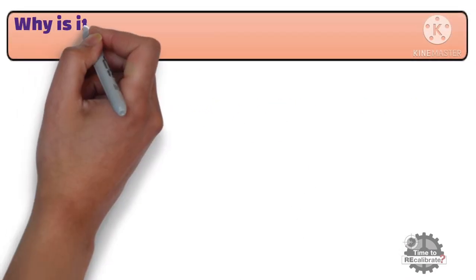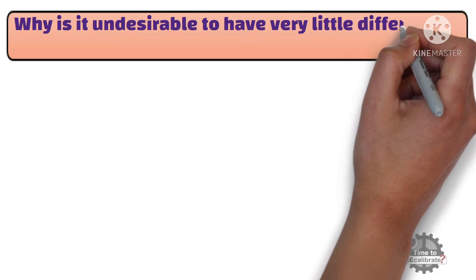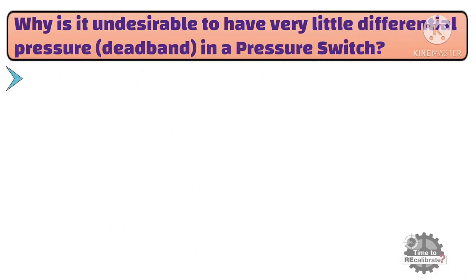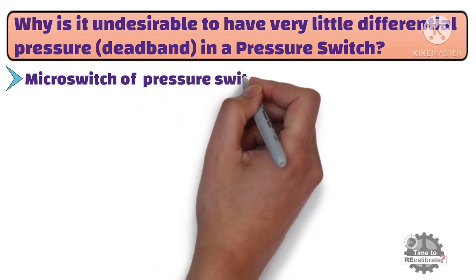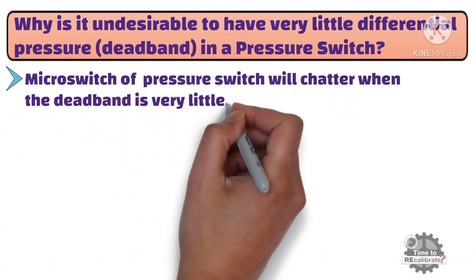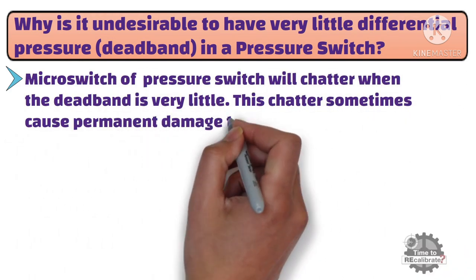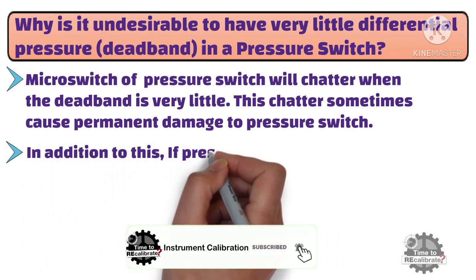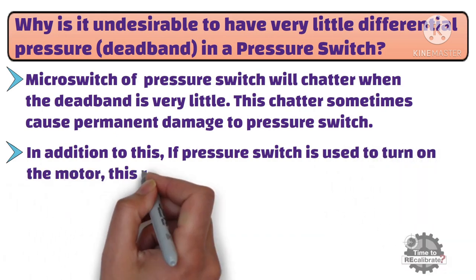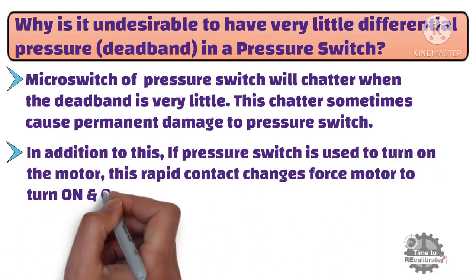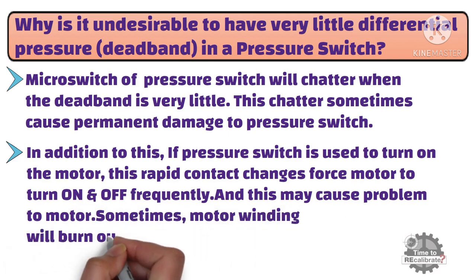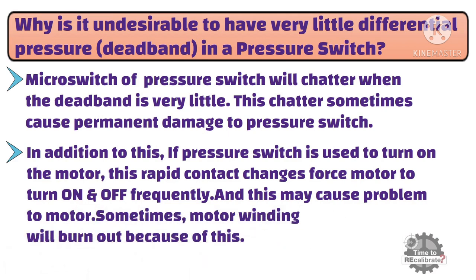Now, why is it undesirable to have very little differential pressure or dead band in a pressure switch? The microswitch of the pressure switch will chatter when the dead band is very small, and this chatter can sometimes cause permanent damage to the pressure switch. In addition, if the pressure switch is used to turn on a motor, these rapid contact changes force the motor to turn on and off frequently, which may cause problems — sometimes the motor winding will burn out because of this.